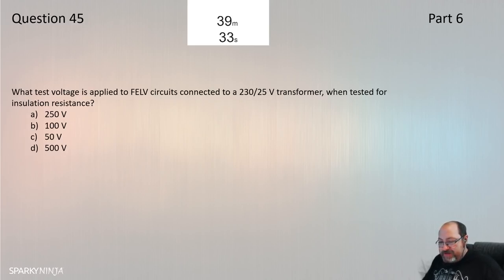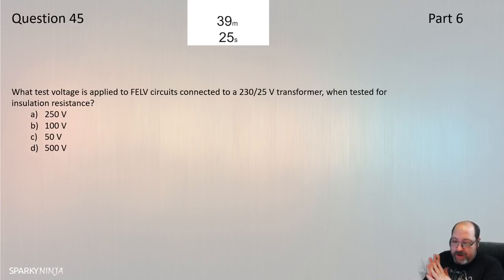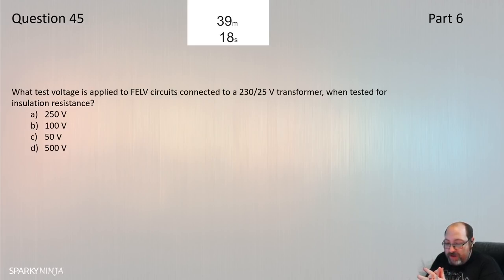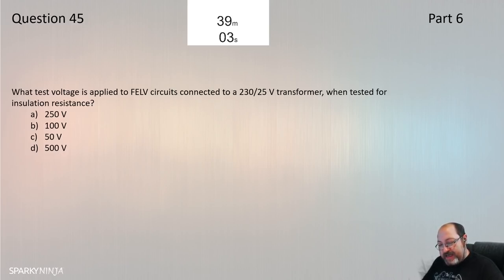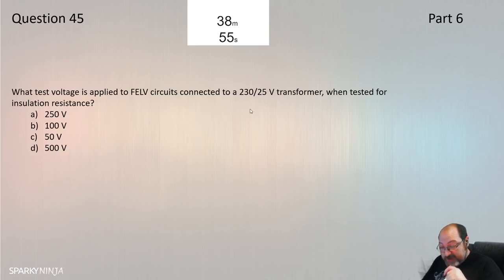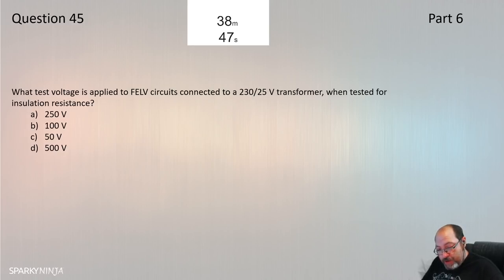Question 45 catches people out. They go to the insulation resistance table at 643.3.2, Table 64, see SELV and PELV listed, and assume 250V. However, the question is for FELV. Two paragraphs below the table it states: FELV circuits shall be tested at the same test voltage as that applied to the primary side of the source. The primary side is 230V, so the test voltage is 500V. Question 45 is D — 500V.